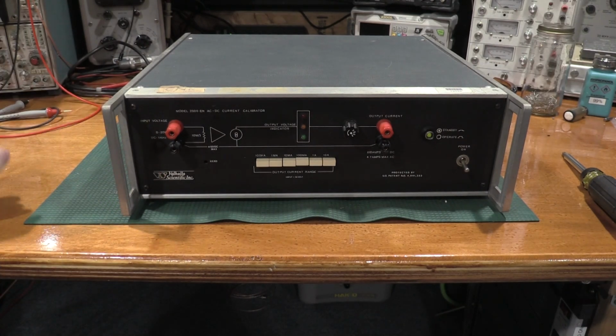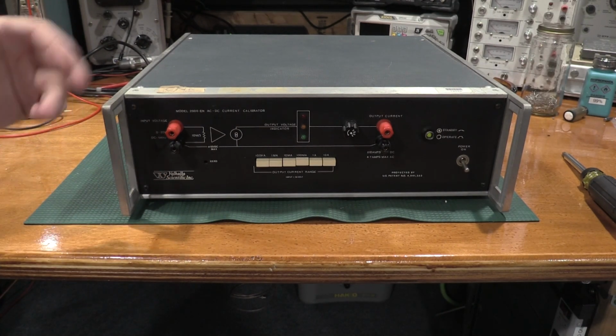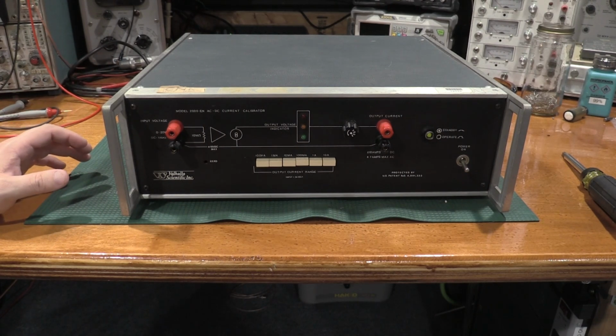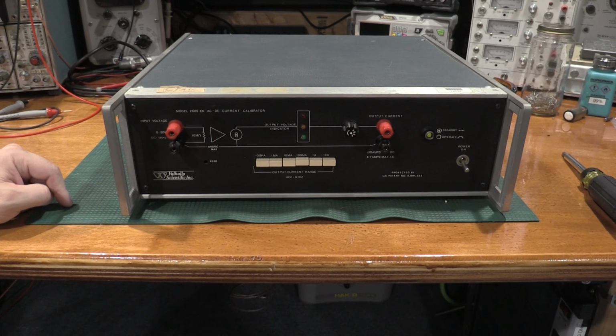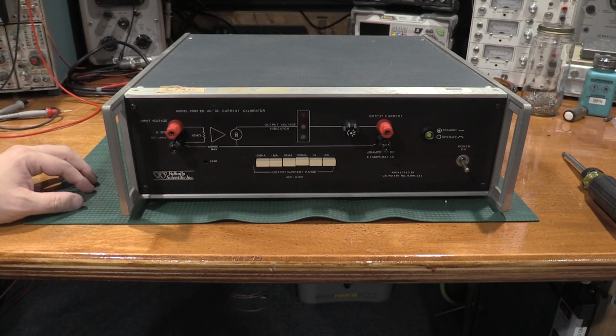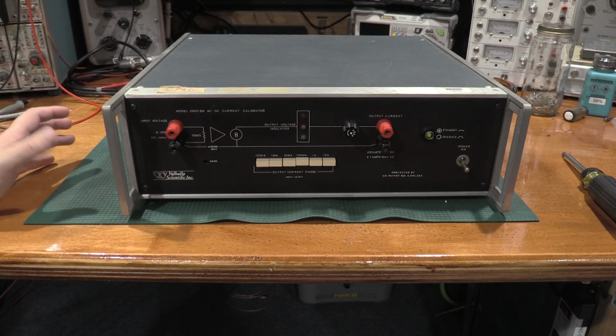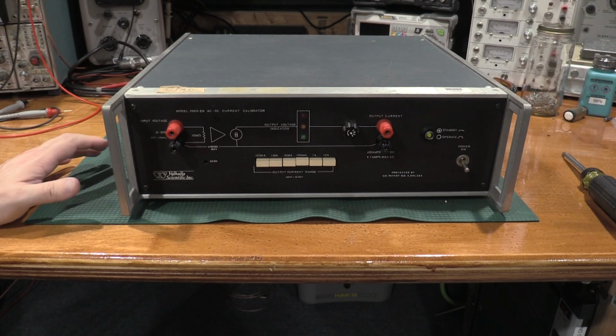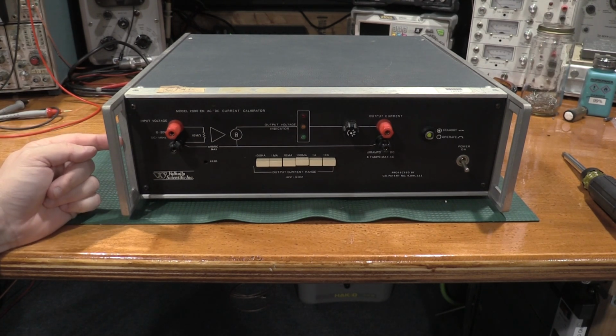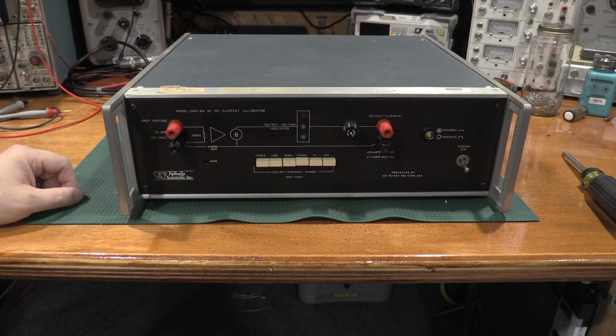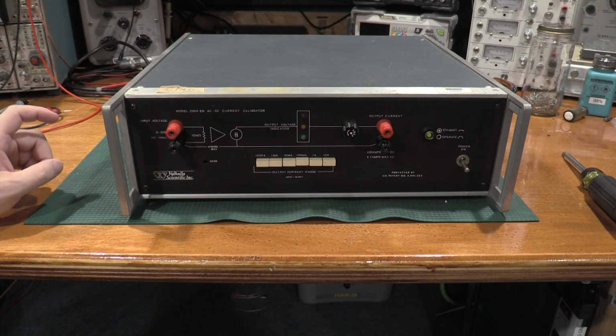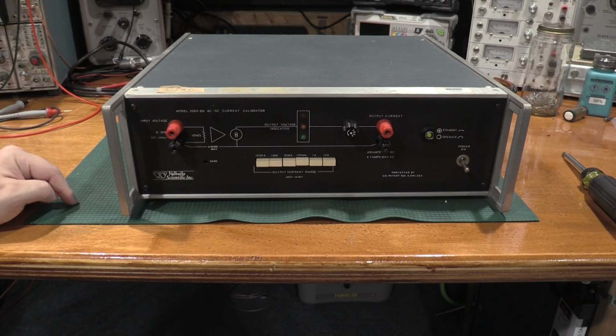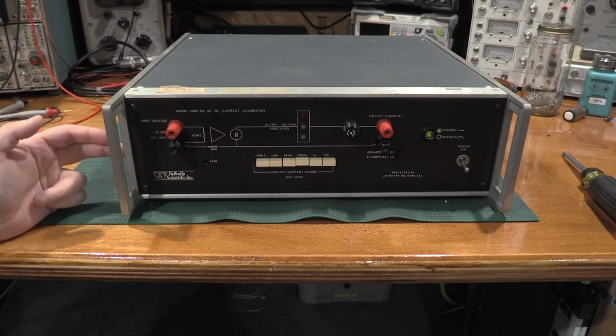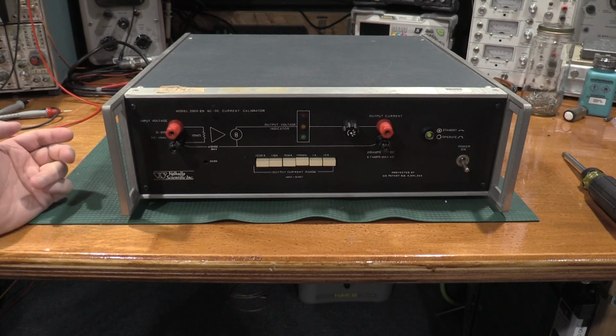This piece of equipment became very critical because in the near future we're going to have a DM 504 on the bench that's microprocessor controlled, and once you start the calibration procedure on that, you can't stop or it doesn't save. So I'm going to need this to get through the current section, because I need positive and negative currents, and I need AC currents as well. And this unit can do all of the above.